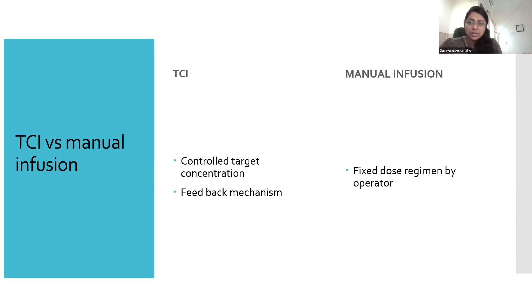So what is the difference between TCI and a manual infusion? TCI is a target controlled infusion. There is a controlled target concentration and it happens by a feedback mechanism. This feedback mechanism provides a more dynamic and effective drug delivery system by using a pharmacokinetic as well as dynamic model that will keep adjusting the dosage of infusion constantly. In manual infusion, it is the work of the operator to determine the dose the patient should get, and it will be given as and when the operator changes the infusion dosages.